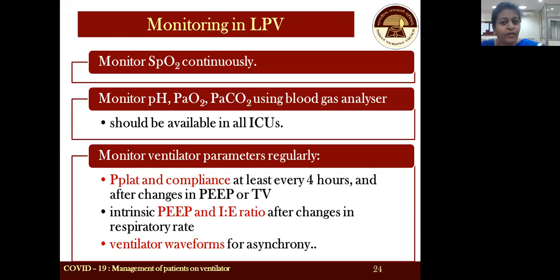The ventilator parameters will also have to be checked and monitored regularly, especially the plateau pressure and the compliance. It needs to be checked every 4 hours or after any change in the PEEP or any change in the tidal volume. Intrinsic PEEP and inspiratory-expiratory ratio have to be checked after any change in the respiratory rate. And if there are any changes in the ABG, usually the rate of respiration and the depth of respiration, that is the volume, is changed. At that time also we need to check the ventilatory parameters. And if any asynchrony is noticed, we have to monitor the waveforms.